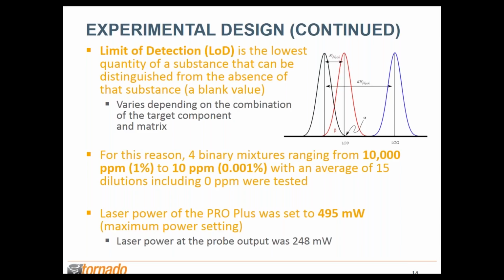Power that was set for the PRO Plus was 495, its maximum power setting. But we're going to transmit through our fiber optic probe, and the probe itself will have an influence on how much laser energy ultimately reaches the sample. And it is that energy that's creating the excitation in the Raman mixture. So it's important to measure that to understand what is the actual power at the probe tip, because different probes can, even if the instrument is the same power, have an impact in that regard. So in this case, I took a coherent, high precision, high accuracy laser power meter, and that was measured to be 248 milliwatts at the probe tip.